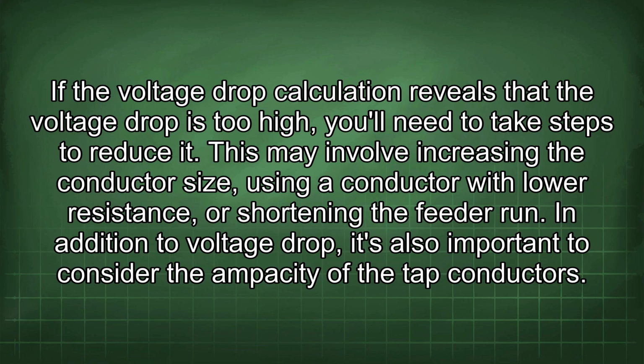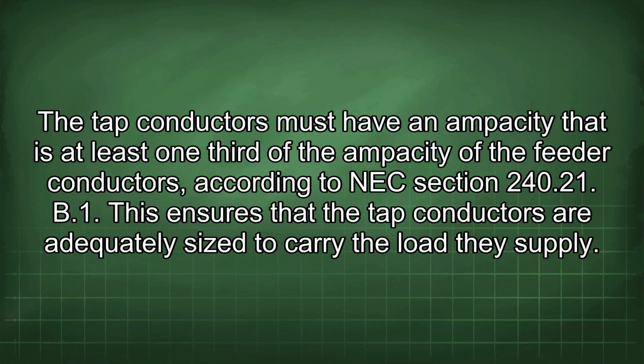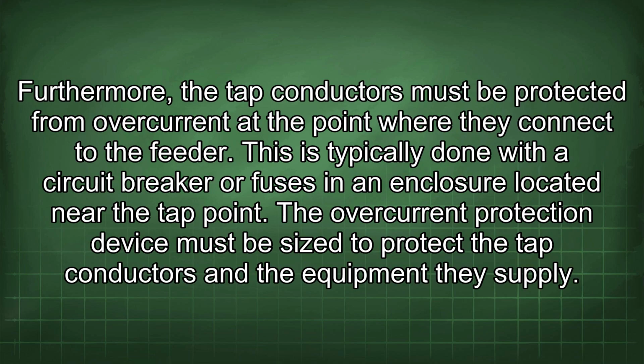In addition to voltage drop, it's also important to consider the ampacity of the tap conductors. The tap conductors must have an ampacity that is at least 1/3 of the ampacity of the feeder conductors, according to NEC Section 240.21(B)(1). This ensures that the tap conductors are adequately sized to carry the load they supply. Furthermore, the tap conductors must be protected from overcurrent at the point where they connect to the feeder. This is typically done with a circuit breaker or fuses in an enclosure located near the tap point. The overcurrent protection device must be sized to protect the tap conductors and the equipment they supply.